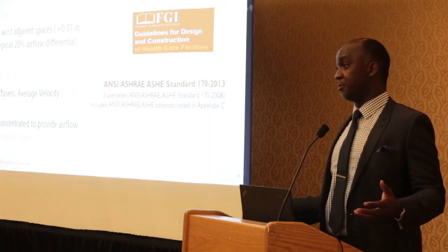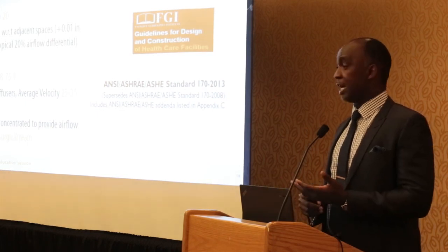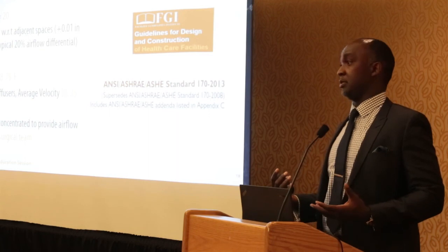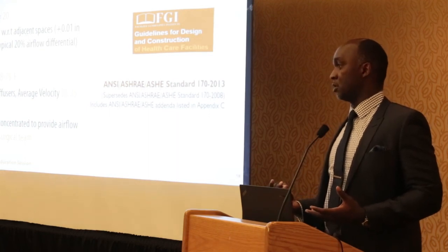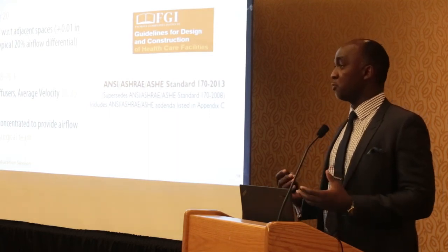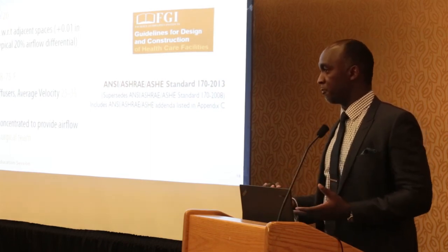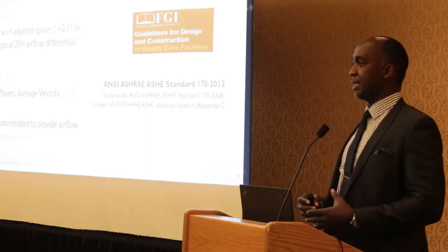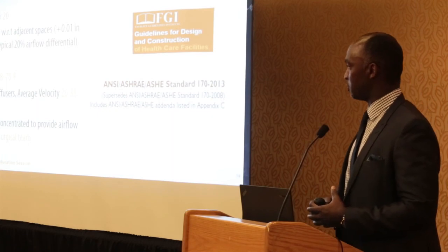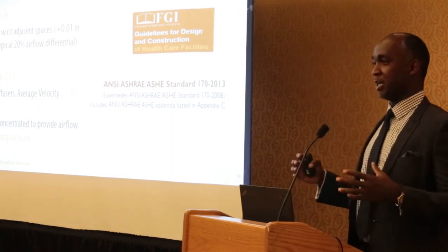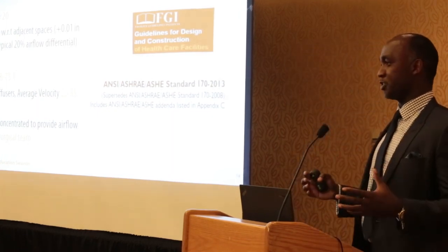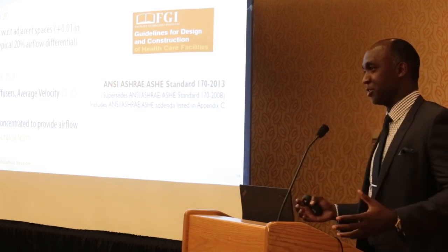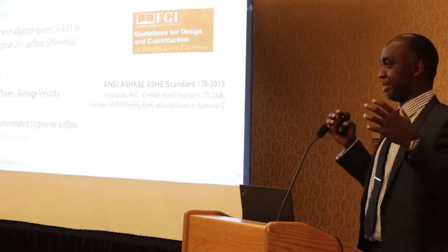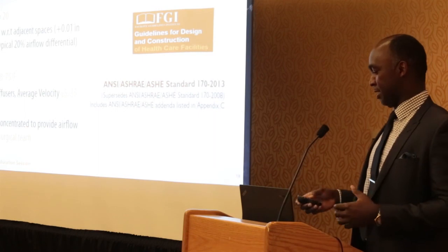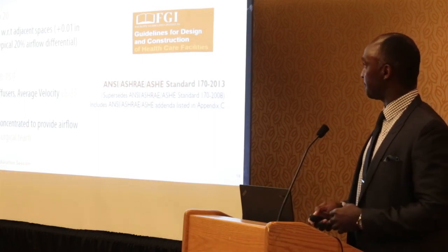It's saying you don't want the air moving too fast. If you're opening a patient, you have to think about hypothermia—is the patient going to be too cold? Is the air moving too fast over the patient, making it uncomfortable? That's why they define a minimum requirement for that as well, over the patient and the surgical team. That's where you're trying to get rid of the bacteria and make sure the area is completely sterile. That's the requirement.